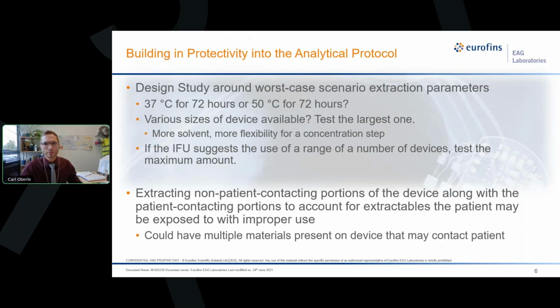So, first steps. Everyone likes to say we don't have a crystal ball, which no one really does. The first steps that should be taken when developing a chemical characterization plan are setting the stage early in the program, building around a worst case scenario on the front end. So when designing a study with worst case scenarios in mind, let's think about the extraction procedure. If your device doesn't degrade at 50 degrees Celsius, then let's, by default, out of the gate, select 50 degrees Celsius for your extraction parameters.